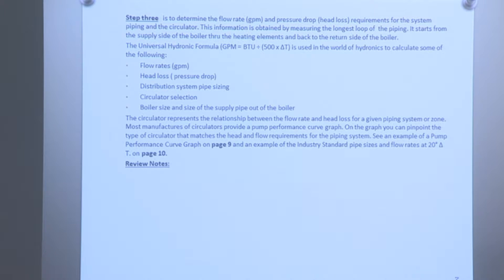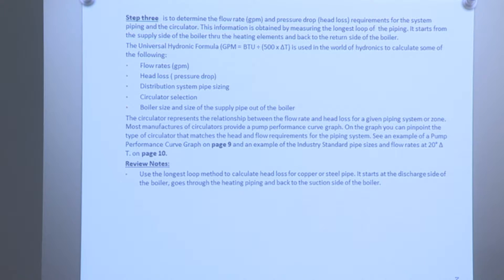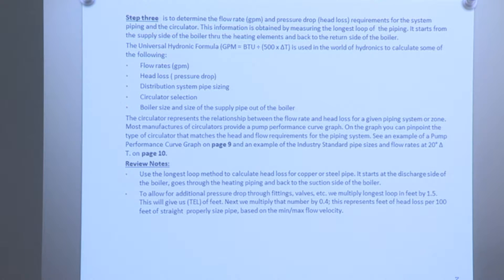The circulator represents the relationship between flow rate and head loss for a given piping system or zone. Most circulator manufacturers provide a pump performance curve graph. On the graph, you can pinpoint the type of circulator that matches the head and flow requirements for the piping system. Using the longest loop method to calculate head loss for copper or steel pipe, it starts at the discharge side of the boiler, goes through the heating piping, and back to the suction side of the boiler. To allow for additional pressure drop through fittings, valves, etc., we multiply the longest loop in feet by 1.5.